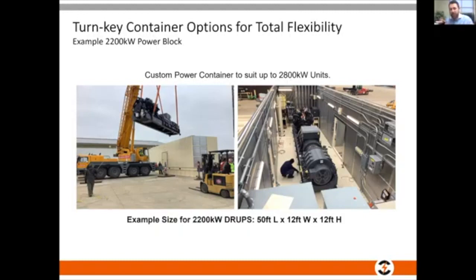This is the third unit for that customer. It's containerized, and this one is custom, so it's a bit bigger than the standard 40 foot. In this instance they've got a really big bulk tank at the bottom, and the container sits on that bulk tank. What happens is we test at the facility - I think this is built by Gertz for those who know them. They build the frame and walls, insert the Drups, put the roof on top, and we do our function test. We then actually remove the Drups, which is a bit odd, and deliver the container as a whole. Depending on size, we might need 2 shipments. But this is a nice visual showing how we containerize these units.